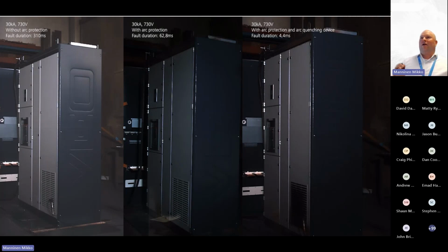We did another test, again related to arc detection, protection, and mitigation. So we can consider this left side here to be the detection part. We detect something with the sensors, but we don't trip with arc protection. It is tripped by the feeder protection. Or we protect with the middle one. We protect with the arc protection, and there is a certain 3 cycles circuit breaker delay. Or we can mitigate. We can reduce the arc incident energy with an arc quenching device. So on the right-hand side, we mitigate by detecting, by protecting, and by mitigating with an arc quenching device. And in this particular test, it was less than 5 milliseconds.